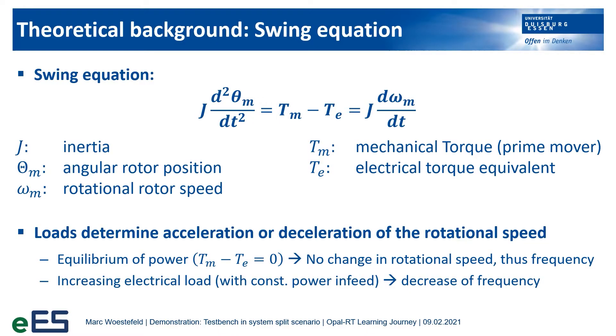First, let us talk about the theoretical background. A simplified method for the description of the synchronous generator behavior is the swing equation. It shows the correlation between acceleration or deceleration of the rotor and the power delivered by the prime mover or consumed by the electrical grid. For a power equilibrium, the rotor will not change its actual frequency. The rotor will be slowed down when the electrical loads are increased with a static power in-feed from the prime mover.